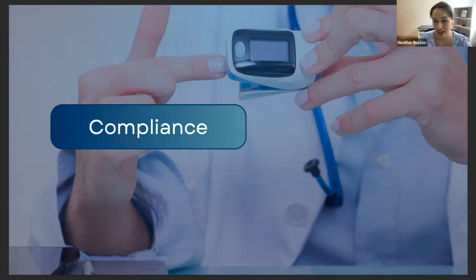Their marketing team started making claims, and what the FDA did was send them something called an "it has come to our attention" letter, which is essentially putting the brand on notice. Hey, you said when you went to market it was only going to be this type of device. You're making these claims. Let us know, where's your backing for this? Do you have the pre-market application? That is not something that goes public per se. And if you ever do receive that, you want to respond. It's something to definitely take seriously. It's the FDA giving you a hint: don't go outside the bounds of what you're allowed to do. And in that case, we were able to remove the claims.